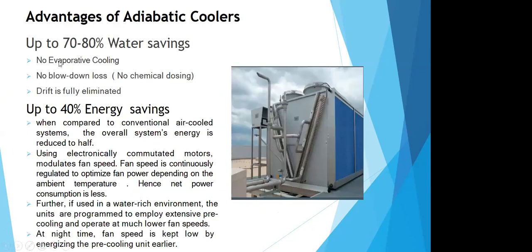So one would naturally ask, how does one incur so much saving in water? Well, the water coming out from the condenser of the chiller is moving into a closed circuit of the adiabatic cooler. So there are no evaporative losses happening. If there are no evaporative losses, there are no drift losses, which you typically see in a cooling tower, and hence there is no blowdown loss as such. So you do not require a chemical dosing system. You do not require special treatment of the water, right? And you would not have any losses occurring due to evaporative cooling. All these put together enable us to reduce the water consumption of the circulating water by more than 80%.